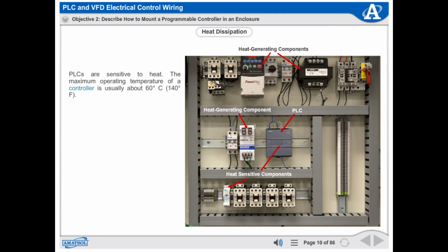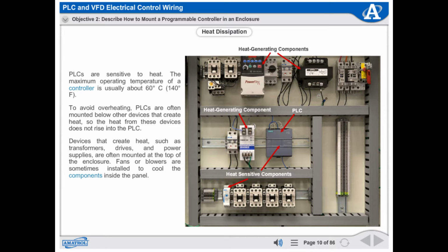PLCs are sensitive to heat. The maximum operating temperature of a controller is usually about 60 degrees Celsius or 140 degrees Fahrenheit. To avoid overheating, PLCs are often mounted below other devices that create heat, so the heat from these devices does not rise into the PLC. Devices that create heat, such as transformers, drives, and power supplies, are often mounted at the top of the enclosure. Fans or blowers are sometimes installed to cool the components inside the panel.